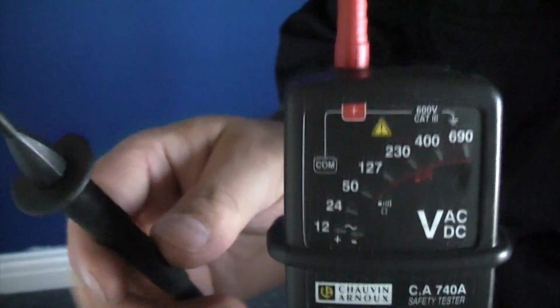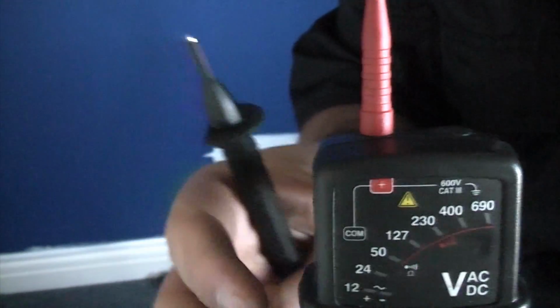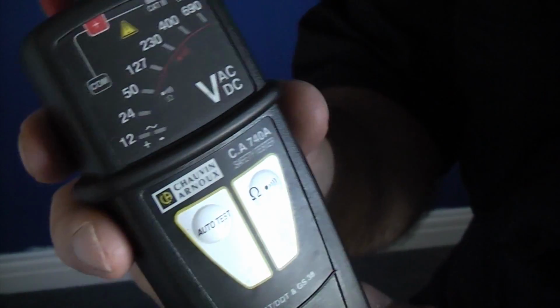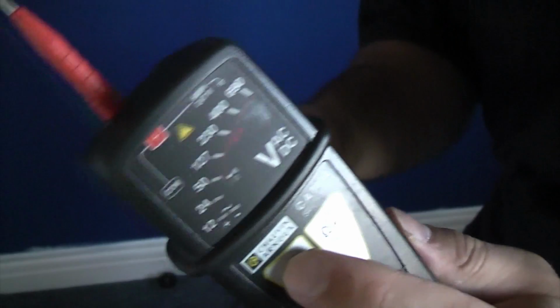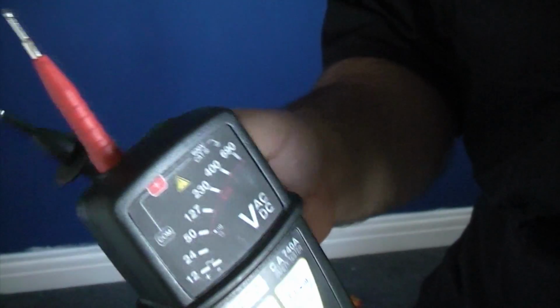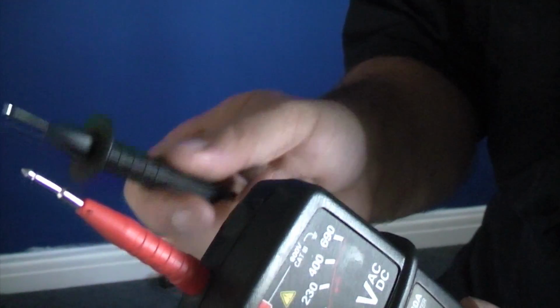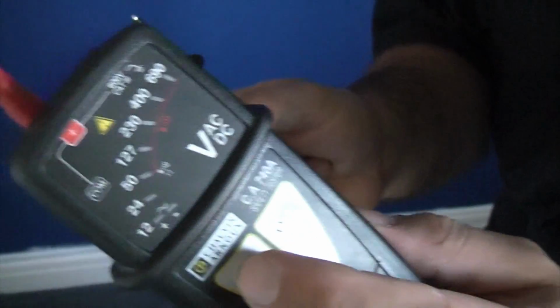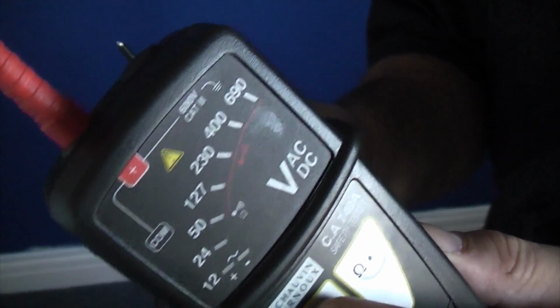This is an approved voltage tester, so don't confuse this with a multimeter. And this particular model also has an auto test function, which is extremely useful because you can test it before you use it. If your particular model doesn't have the auto test function on it, you need to test that your meter's working before and after the isolation. So we're just going to test the meter now, and you can see that that's working.